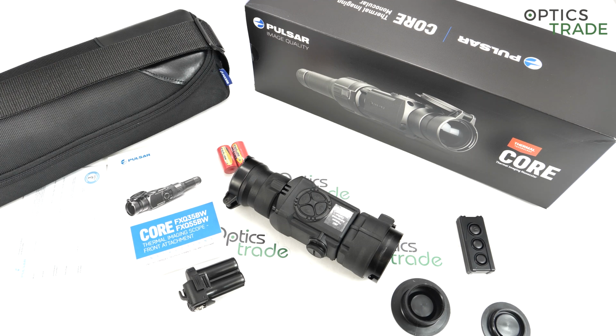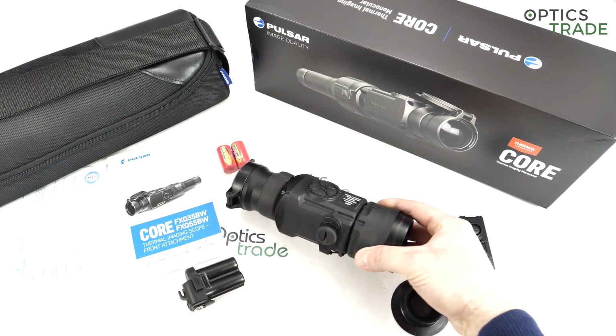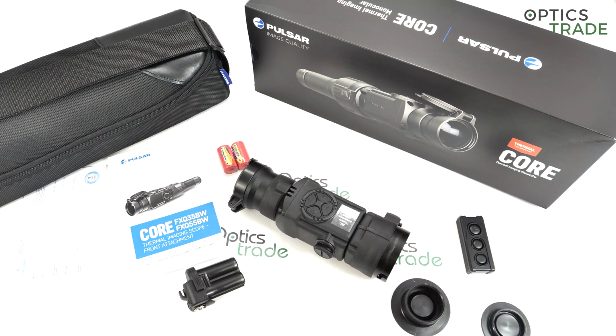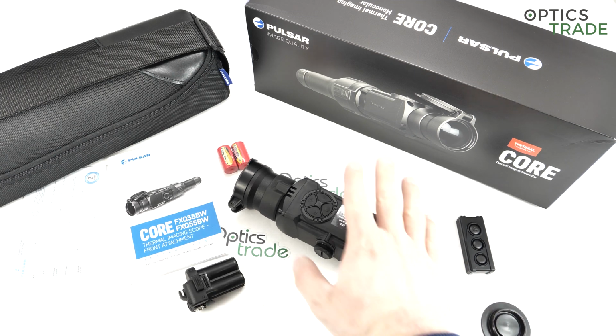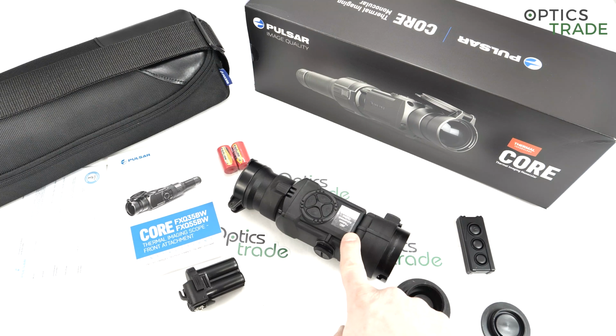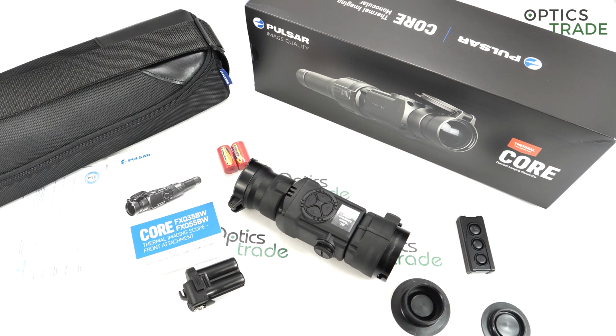The differences were that they all have the same housing, the same appearance, the same looks and the same design. The first generation featured a sensor which had a 25 micron pixel pitch, or the size of the pixels. Then the second generation had a 17 micron pixel size, and now the third generation is basically the same, only the color of the display changed from green to black and white. So it's basically the same device as generation 2, only the display color is different.